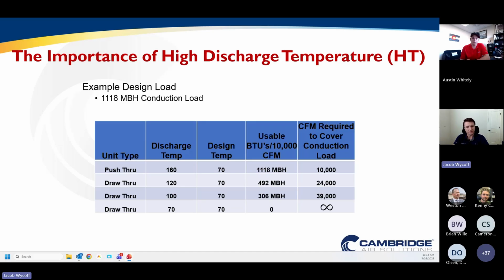But if we restrict the discharge temperature to 120 degrees, like you typically see with draw-through equipment, you can see they only get 492 MBH of usable BTUs for every 10,000 CFM. Because the discharge temperature is a lot closer to the space temperature, you're getting less usable BTUs. And you can see now it requires 24,000 CFM to be able to cover the conduction load of the space. I think we can all see the issue with providing 2.5 times the airflow. You're going to have equipment that's much larger, more costly, and difficult to install.